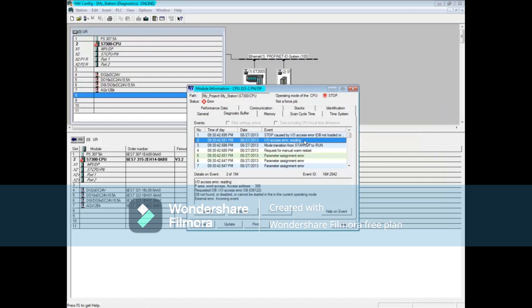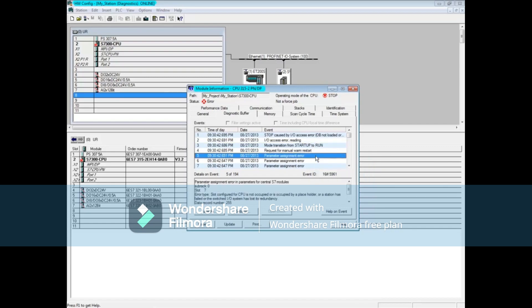Message 5 says there was a parameter assignment error with slot 7. Slot 7 in this rack is an analog module. The reason for the failure is not yet clear.